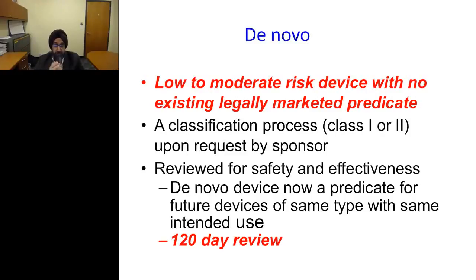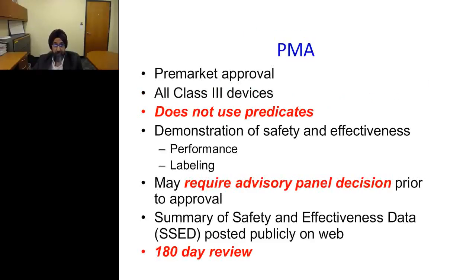FDA was very clear that for a low to moderate risk device where there is no predicate, you can still go to FDA through the De Novo pathway and they will help you decide if the device is ready for clinical use and is safe. The De Novo process can take up to 120 days, a bit longer than the 510(k). Class III devices require even more time, involving multiple levels of meetings with advisory panels at different layers of FDA communication.